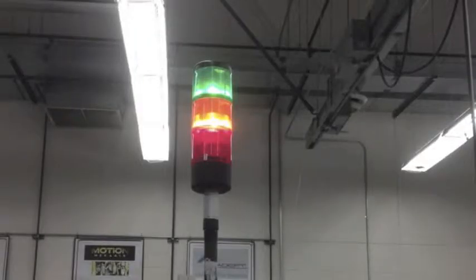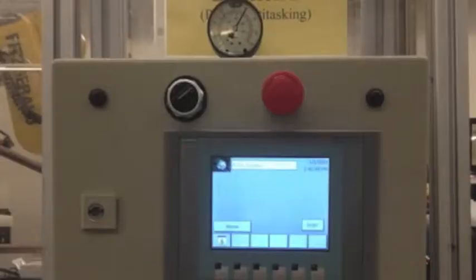These are the stack lights. Green indicates when the program is running, amber for when the MCR is on causing power to come high, and red for when there is a fault in the program. This is our normally closed E-stop. When pressed, the FANUC UOP hold is faulted, causing the arm to halt.